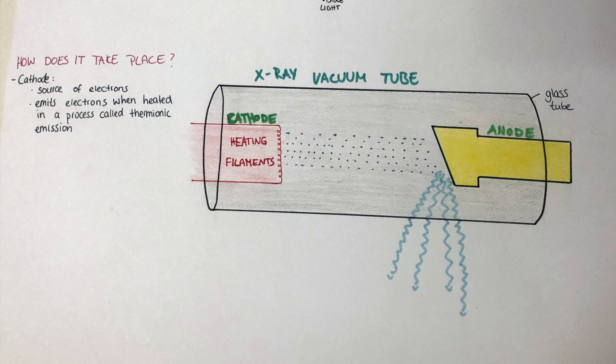So how does it take place? We have a cathode, which you can see here, which is the filament within the x-ray tube that acts as our source of electrons. The cathode is a metal surface connected to an electrical current so it can be heated up. This is necessary because electrons are normally stably staying within the metal of the cathode, since electrons are attracted to the positive nuclei of the metal atoms. When we heat the cathode up to a very hot temperature, it can release electrons — a process we refer to as thermionic emission.